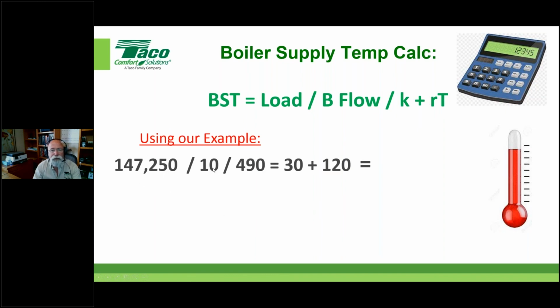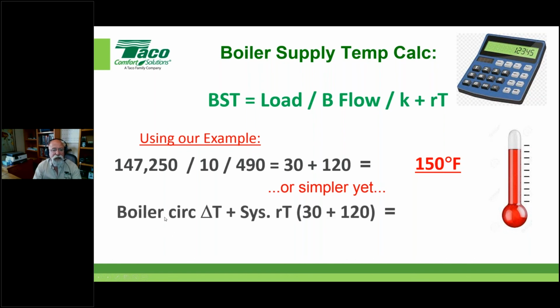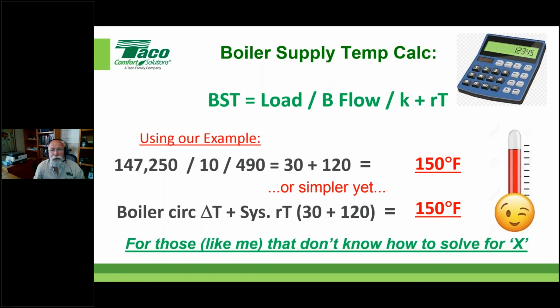So that's what this would look like, okay? 147,250 divided by the flow of 10 gallons a minute. My constant's 490. It gives me a 30 plus 120. 120 plus 30 is 150. Or even simpler, you just take the boiler's delta T that you used and add it to the system return temperature. So 30 is my boiler delta T that I used, and I got a return temperature of 120. 120 plus 30 is 150. And that's just for us folks that don't know how to solve for X.